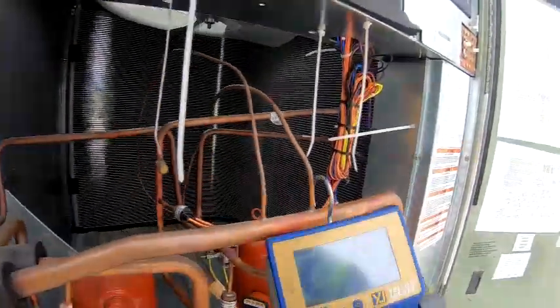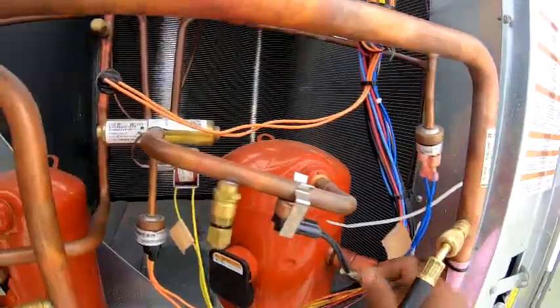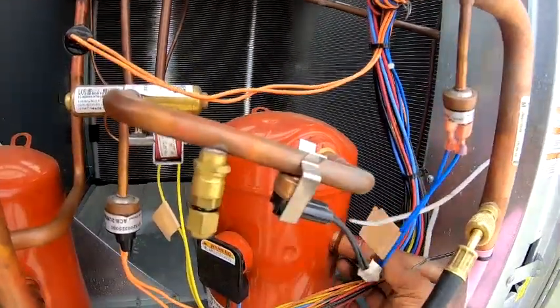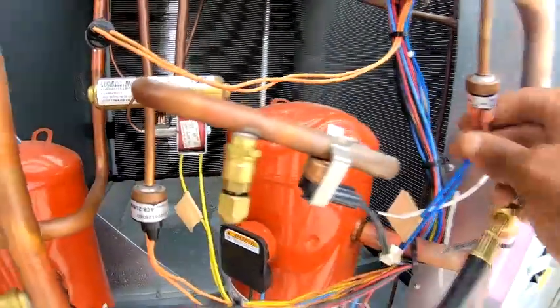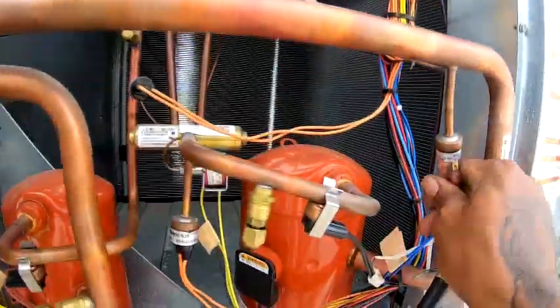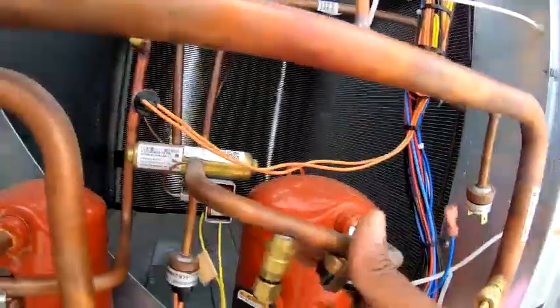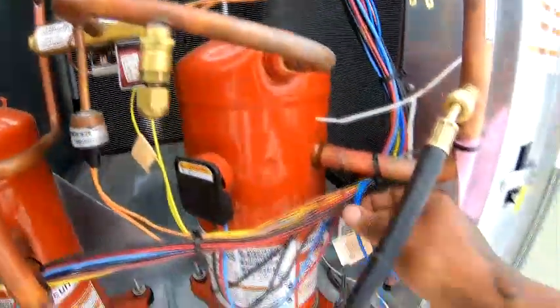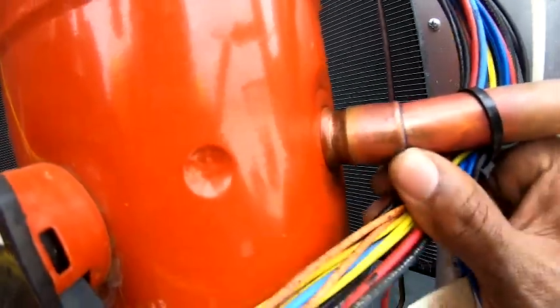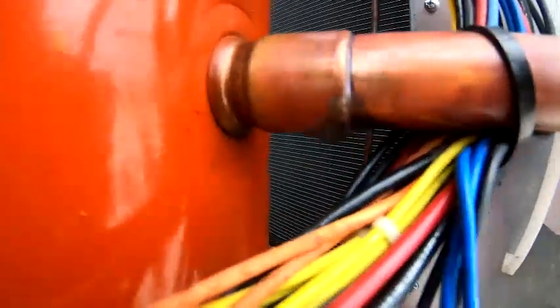Before I even pulled the leak detector out, I started hearing it when I got above 200, and the leak, I can even feel it. Looks like this copper cracked right here. Take this out, but it's right there on that suction line. I start hearing it immediately, like it's on that weld down here.